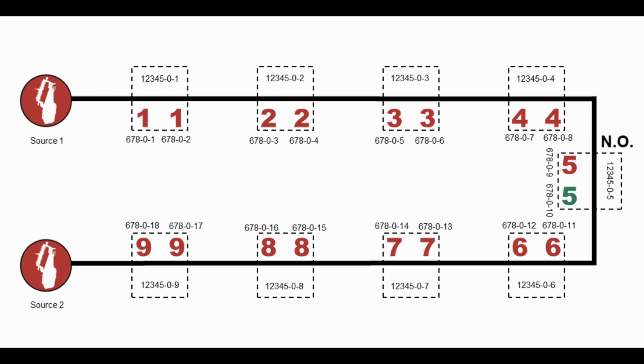An example loop, including 8 normally closed transformers and 1 normally open transformer, is shown here. S&C recommends exporting a diagram of each loop where the EdgeRestore system is to be installed from the utility's Geographic Information System, GIS. Record the transformer designations of each EdgeRestore system-enabled transformer along with the designations of the load and source side cables for normally closed transformers.